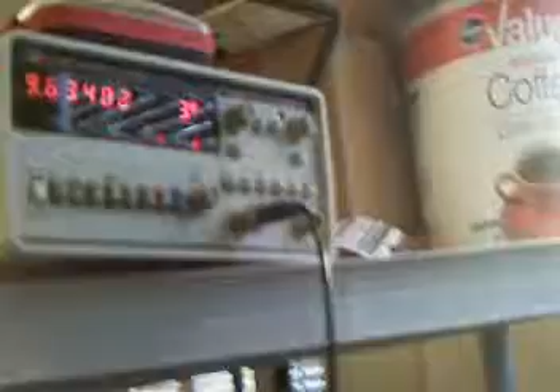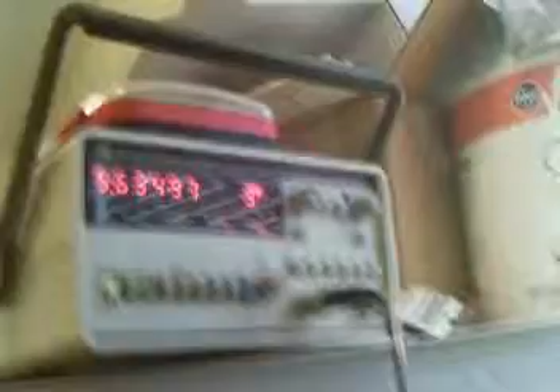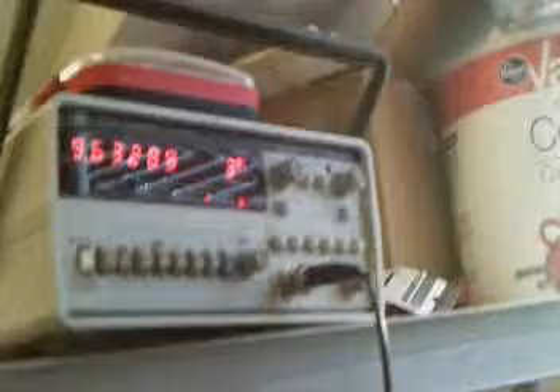Up here on the frequency counter, I have the CF pulse output of the ADE chip. I am at 9.6 kc, and I can scale that frequency, and I'll measure that frequency and translate that to watts instead of using the watt register with the ripple. That's a much more accurate way to do it.